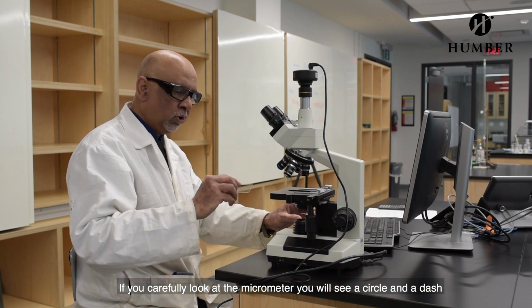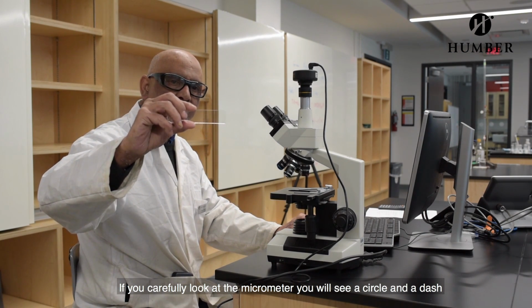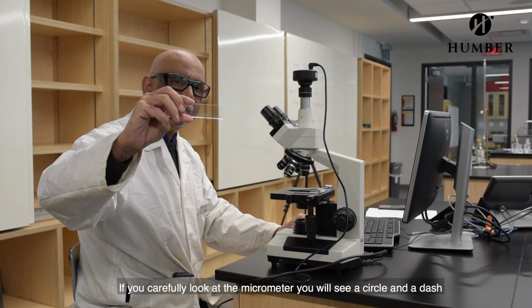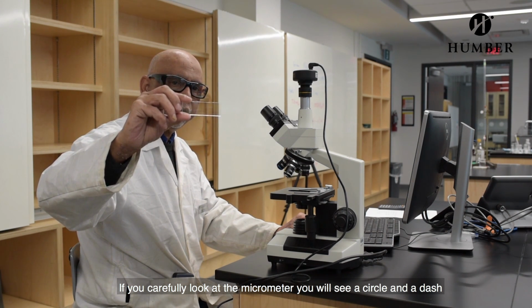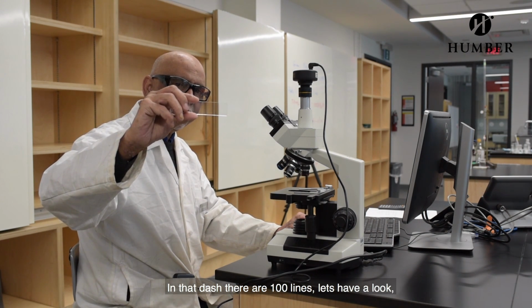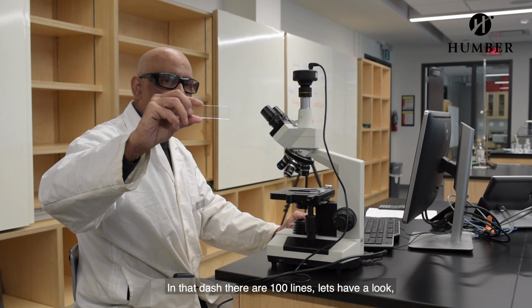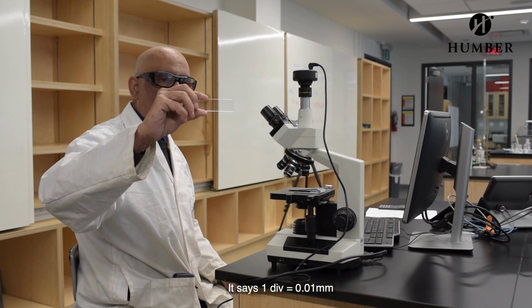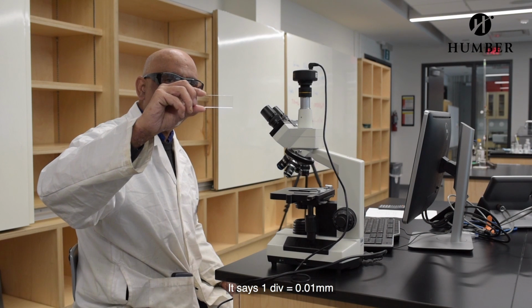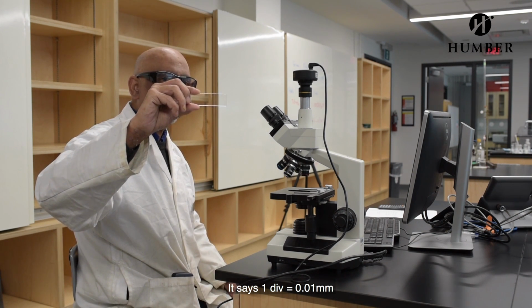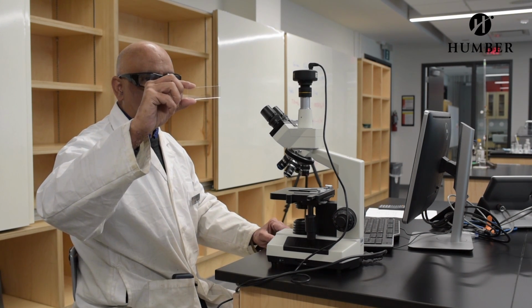So your screen has enlarged a lot. To calibrate the microscope, we have what is called a stage micrometer. If you carefully look at the stage micrometer, you would see a circle and a dash. In that dash, there are 100 lines. So let's have a look. It says 1 division equals 0.01 millimeter. So this is what it says.